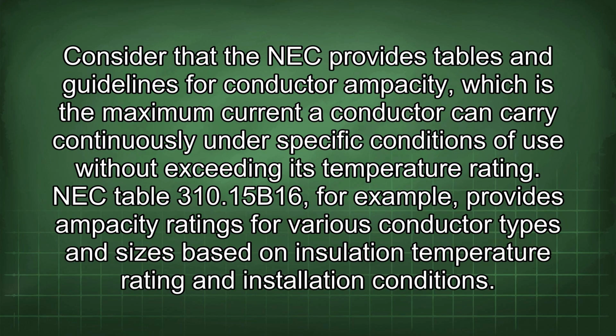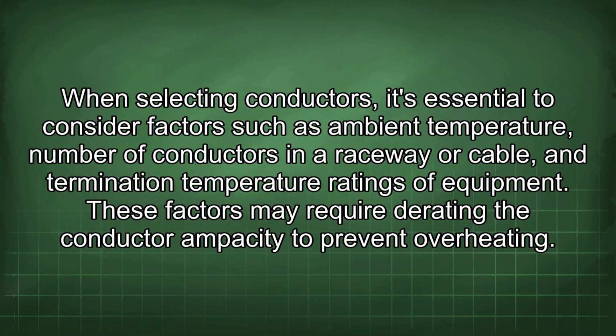installation. Consider that the NEC provides tables and guidelines for conductor ampacity, which is the maximum current a conductor can carry continuously under specific conditions of use without exceeding its temperature rating. NEC Table 310.15(B)(16), for example, provides ampacity ratings for various conductor types and sizes based on insulation temperature rating and installation conditions. When selecting conductors, it's essential to consider factors such as ambient temperature, number of conductors in a raceway or cable, and termination temperature ratings of equipment. These factors may require adjusting the conductor ampacity to prevent overheating.